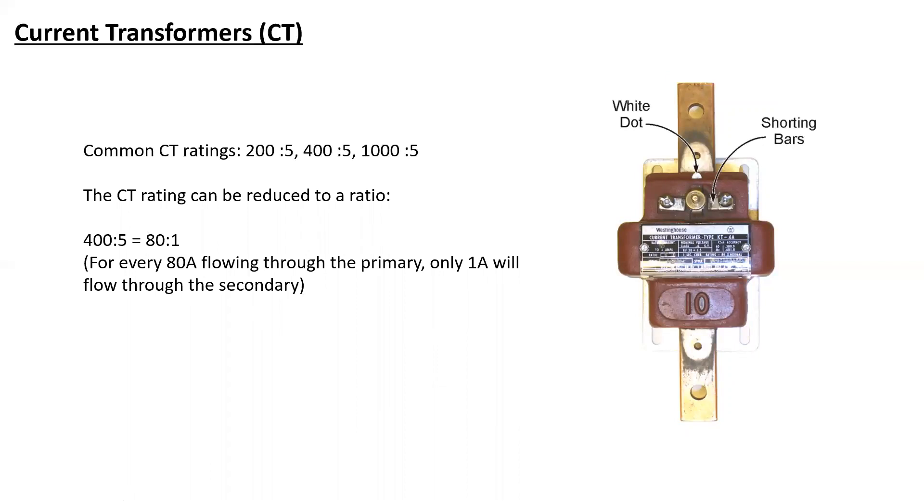And that's because these were primarily used for utility metering. And the utility's energy meters would be calibrated to accept a maximum value of current. Now, it does not mean that this particular CT can handle a maximum of 400 amps. It can handle quite a bit more. So, with this ratio of 80 to 1, it means that for every 80 amps that flows through the primary, one amp will flow through the secondary.